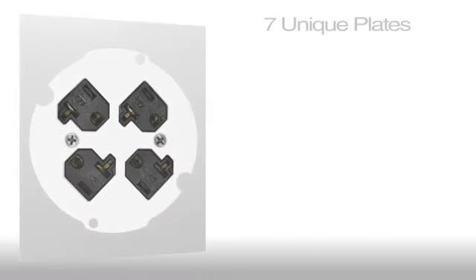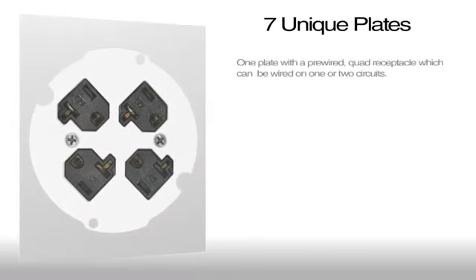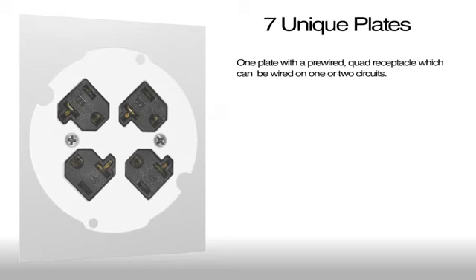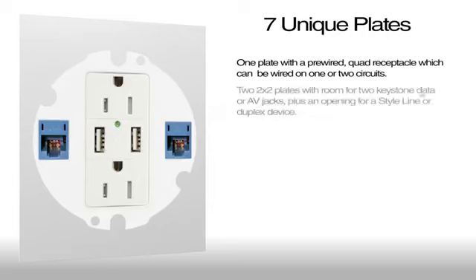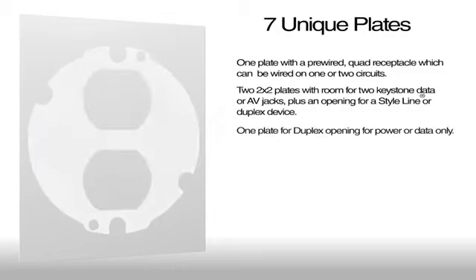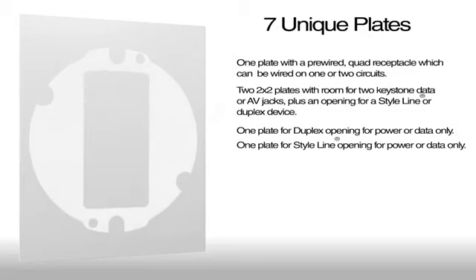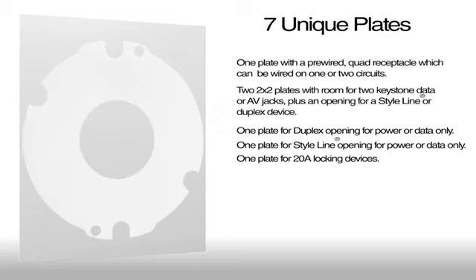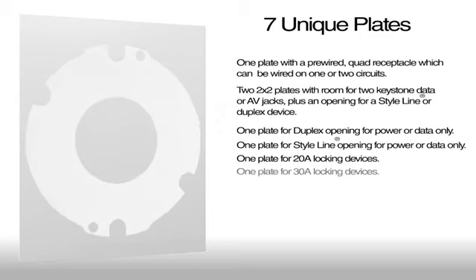Hubbell offers seven unique plates. One plate with a pre-wired quad receptacle which can be wired on one or two circuits. Two 2x2 plates with room for two keystone data or AV jacks, plus an opening for a style line or duplex device. One plate for duplex opening for power or data only. One plate for style line opening for power or data only. One plate for 20 amp locking devices and one plate for 30 amp locking devices.